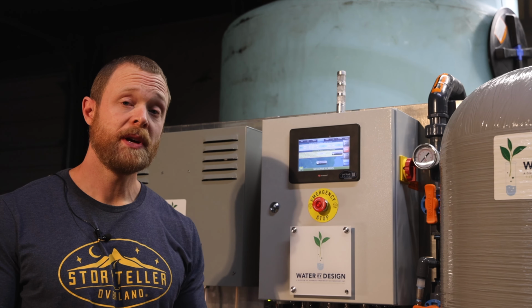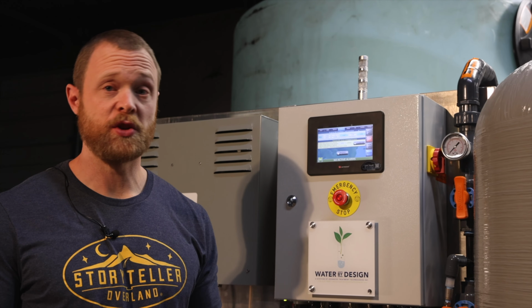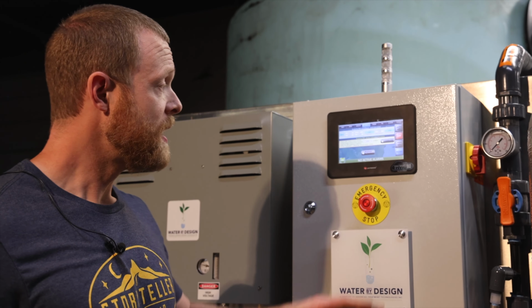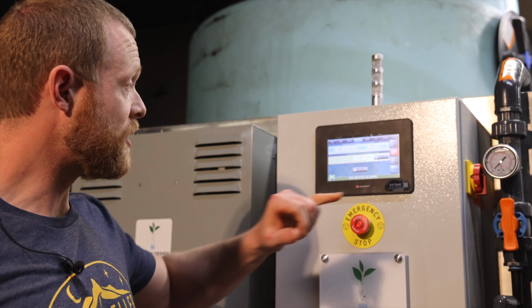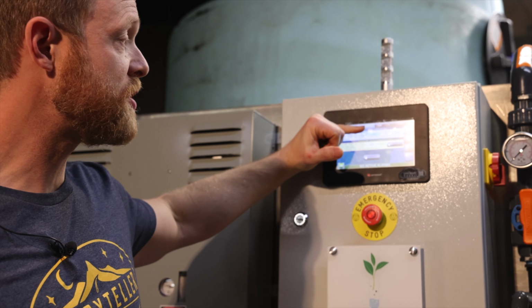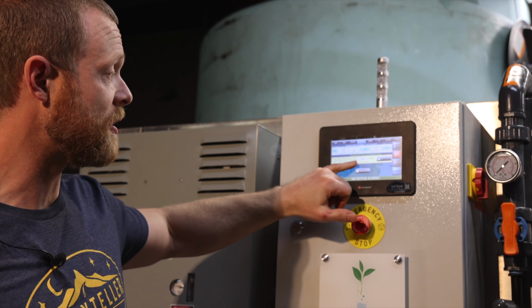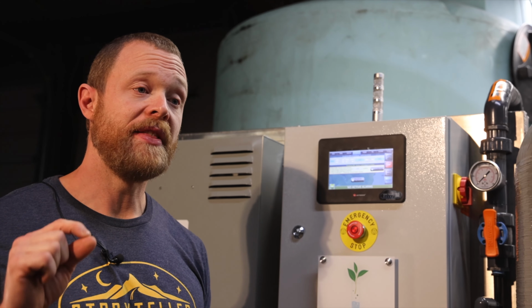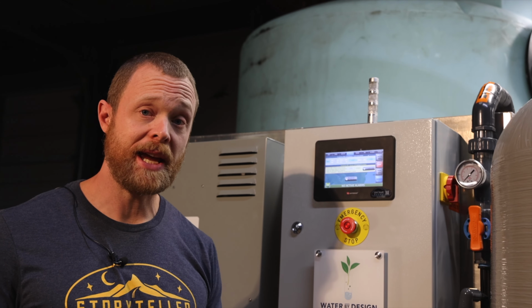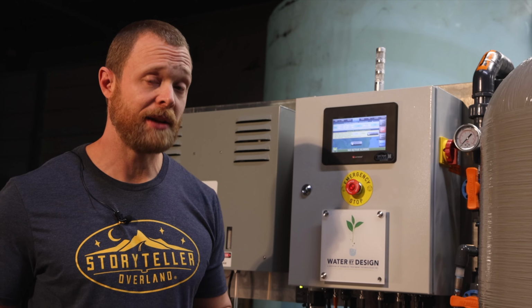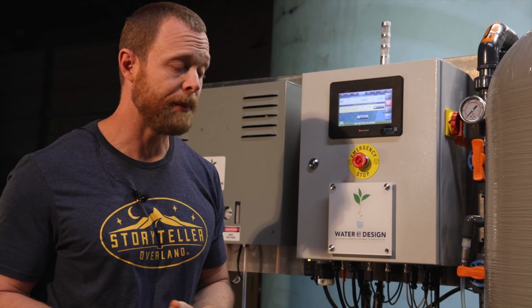Now, to ensure that our probe is properly calibrated, there's one additional step that we need to take. When you push the calibrate button, you will see the actual value come up to 470 that will match the value here that we're calibrating to. But that in and of itself does not necessarily mean that the probe is entirely calibrated correctly. Again, there's one additional step. Occasionally, the salt bridge on the tip of the probe is going to need to be rebuilt. Now, we've made a separate video about that, so you'll want to go over there if you think that you need to do this, and all of those instructions will be there.